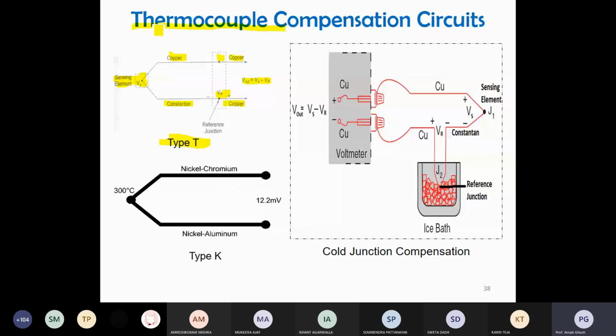In the compensation circuit, the next one is type K. Type T uses copper constantan, while type K uses nickel chromium and nickel aluminum. You get about 12.2 millivolt at 300 degrees centigrade.